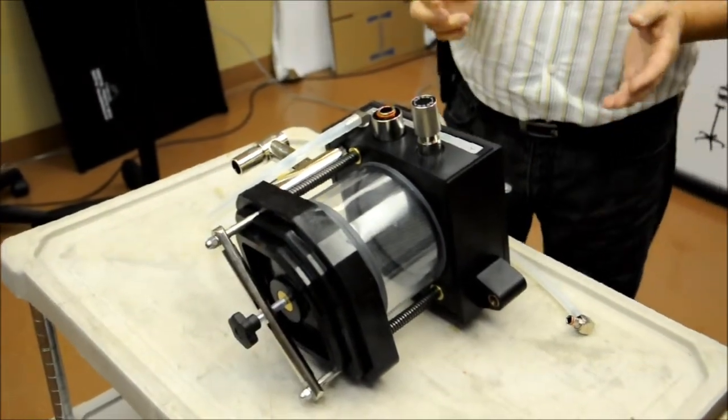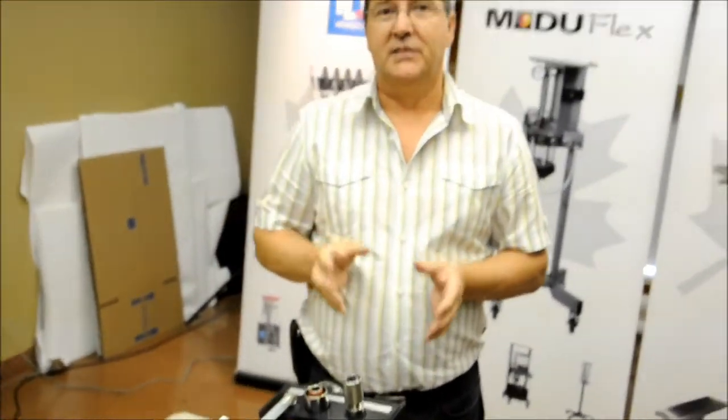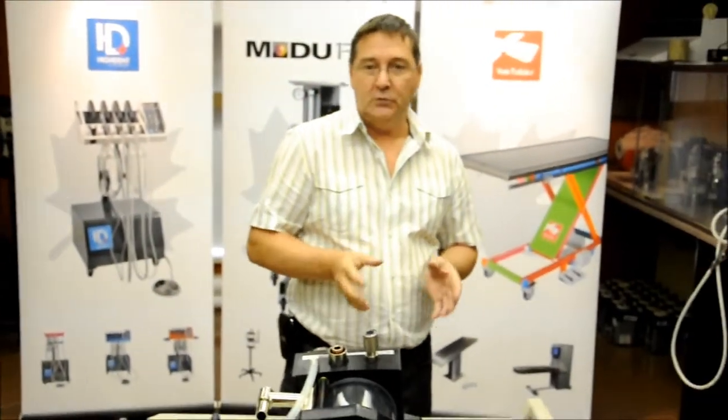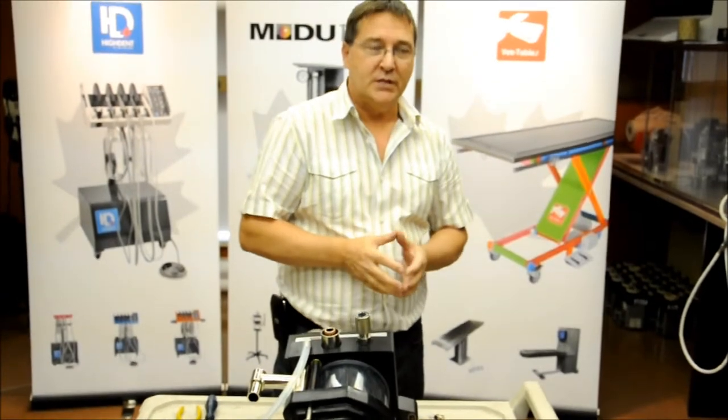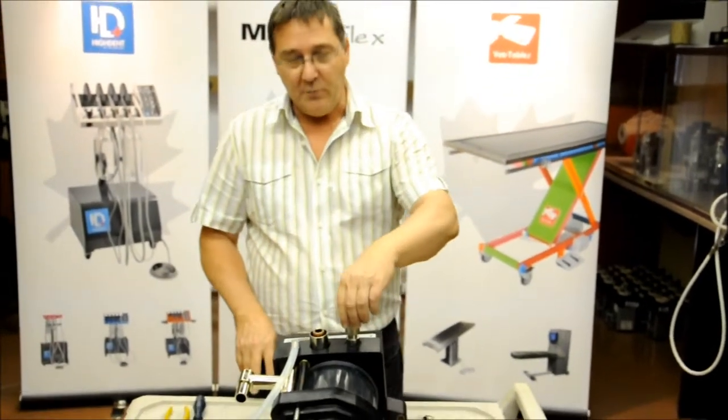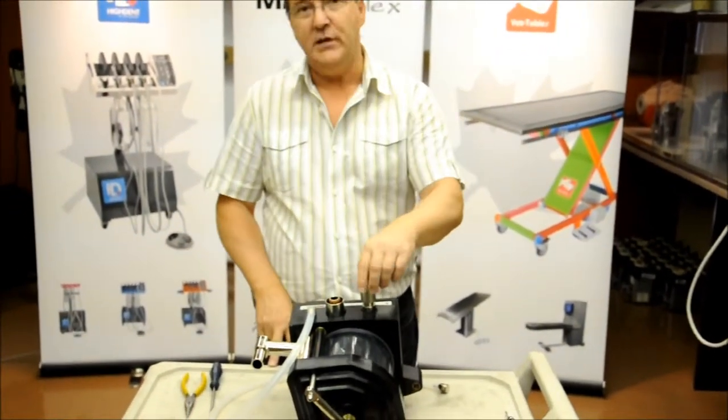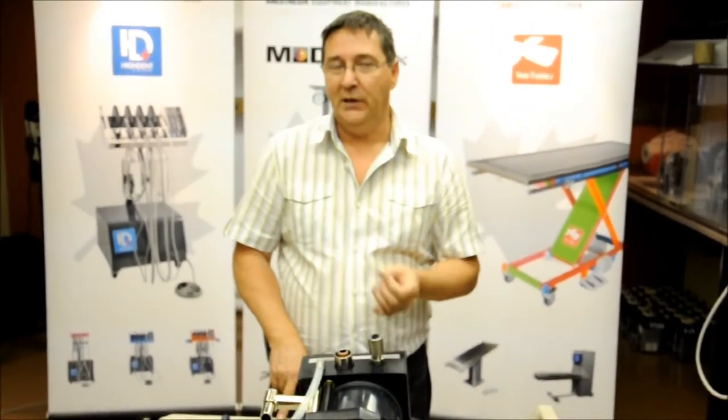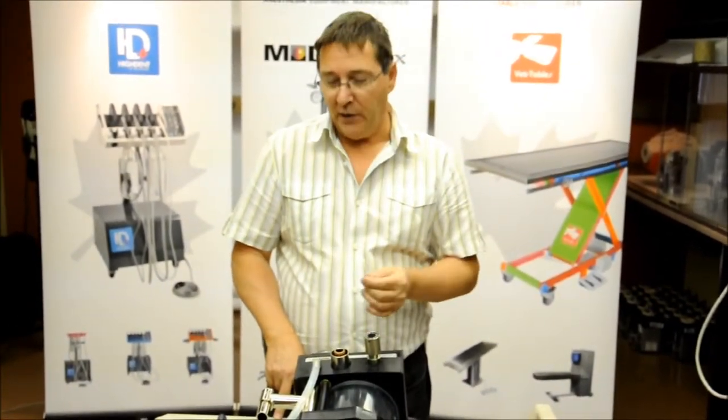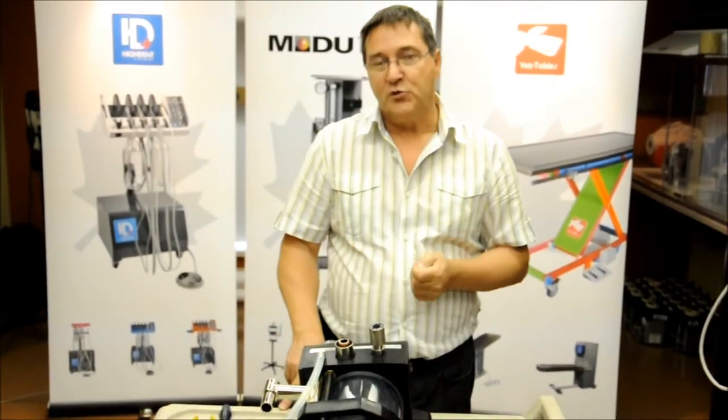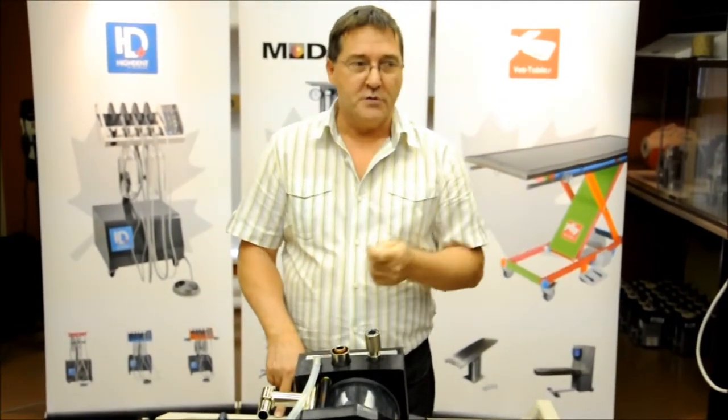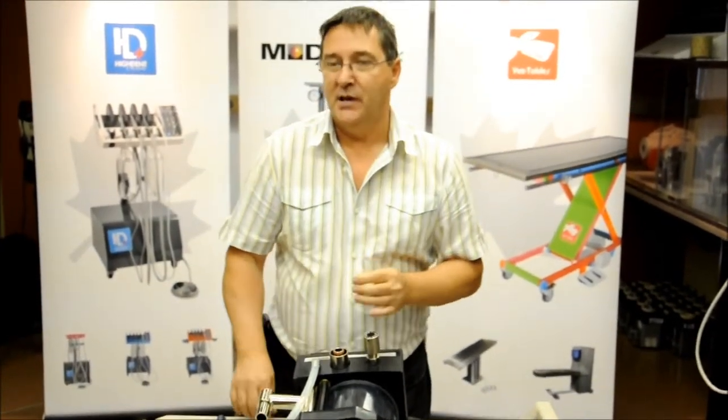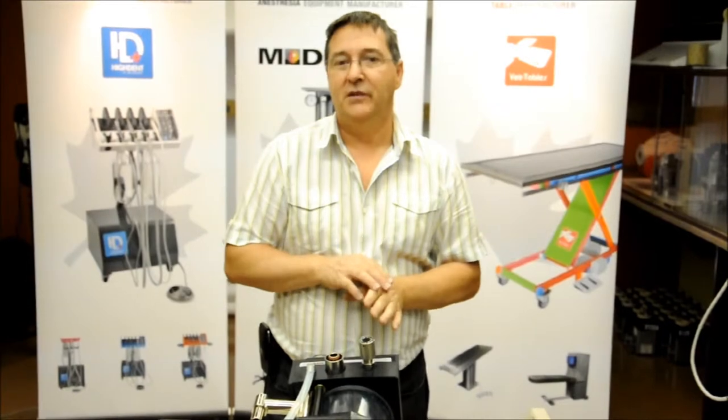Now all we have left to do is test our machine to make sure that everything operates properly. The way you will do that is you will take your breathing circuit with the pop-off valve on the machine fully open, turn your oxygen flow meter up to one liter per minute. At one liter per minute, you will obstruct the end of your breathing circuit with your thumb and watch the bag inflate on the machine. Leave the bag fully inflate.